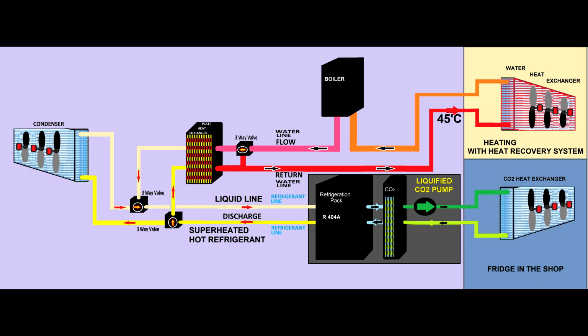This type of refrigeration equipment uses carbon dioxide to transport the energy and to remove the heat from the product in the store. This carbon dioxide circulates through a heat exchanger. It is under a lot of pressure, about 33 bars. It's a subcritical system. And when you use a heat recovery system, you have to make sure that you're not dropping the pressure of the primary refrigerant too much. Otherwise, you might ruin the refrigeration process, the pressure will grow on the carbon dioxide side, and the carbon dioxide will be released into the atmosphere.